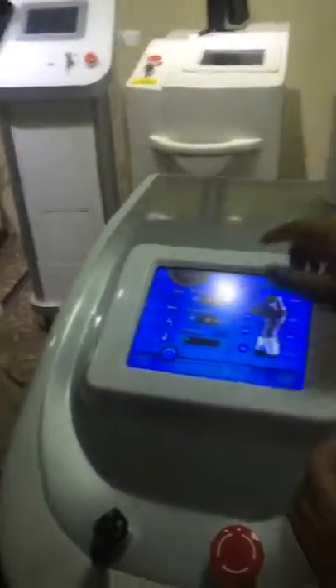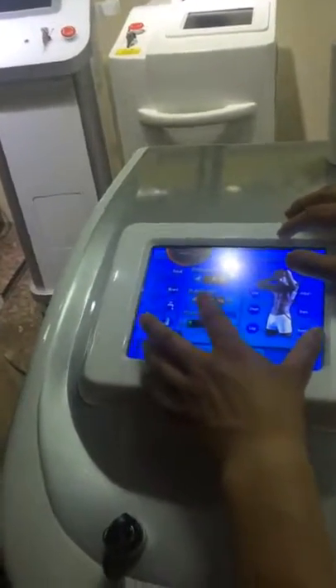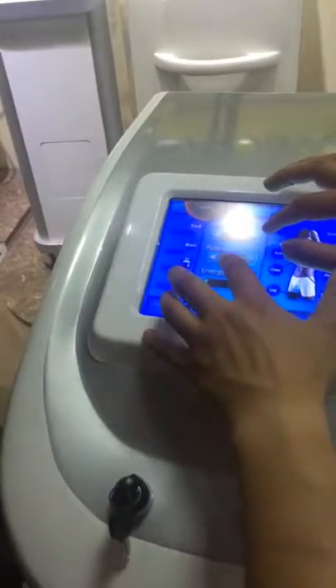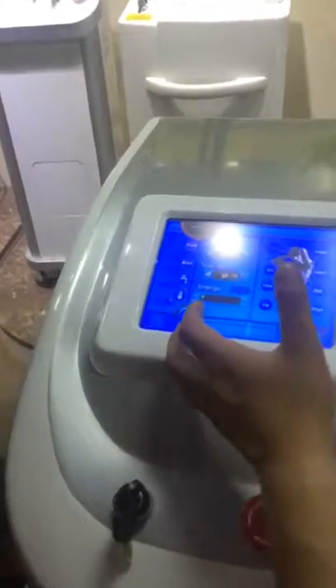Okay, and you can see now frequency is 8. Max power values is 50, and if you increase to 10, it will reduce by itself — you can see? It's to protect the skin.